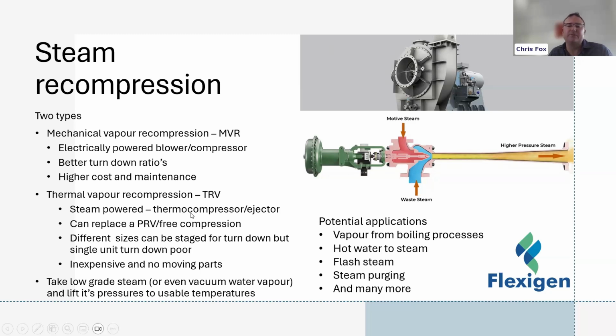Basically, you can use a device called a thermocompressor or an ejector to compress steam vapor. It will do it with any gas, basically. It takes a higher pressure motive input and a lower pressure or even vacuum input and discharges an intermediate pressure gas from there. And in a steam system, these are regularly used to create vacuums. They're regularly used to compress a low-grade steam to bring it up to a temperature where it's reusable again. Big advantage of these guys is they have no moving parts. They're quite inexpensive. They have very poor turn down compared to an MVR, but because they're cheap, you can manage turn down by having a series of different size units which switch on and off in stages.